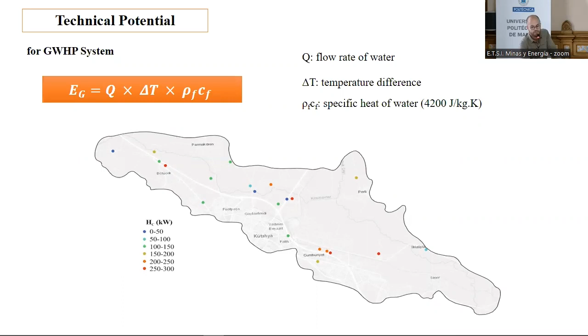This is how we calculate technical potential for shallow geothermal systems. For groundwater heat pump systems, we use this equation, where Q is the flow rate of water, Delta T is the temperature difference of the system (usually taken as 3 or 4 Celsius), and rho F and CF represent the specific heat of water, which is a constant value.